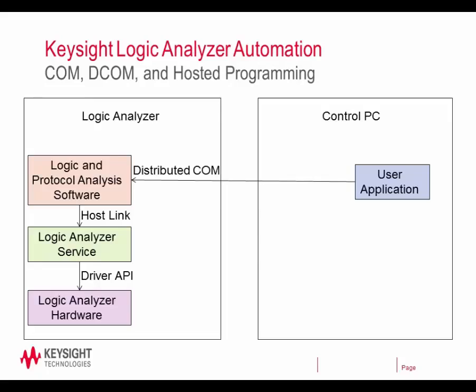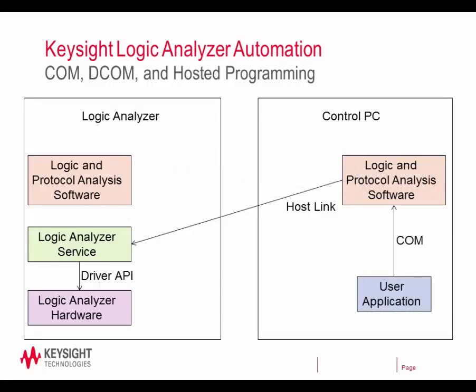That said, we have a better option. Knowing that in that kind of context we don't have a domain controller in the middle and that we're working on a direct LAN, we can switch over to using a hosted setup. In the hosted setup the logic and protocol analysis software ends up running on the control PC. In all of these cases you end up having to install it there anyway, but here you actually truly run it on the control PC and basically turn off the logic and protocol analysis software on the analyzer itself. This allows you to write COM programs just like you had been on the analyzer, except they can run on a separate control PC that might be managing other instruments without bogging down the analyzer with code that would slow down your acquisitions.